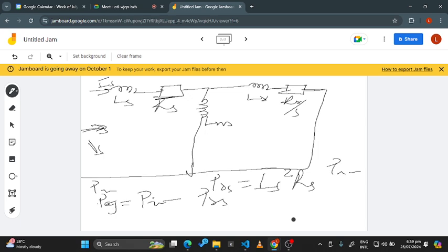As it goes to the rotor, the rotor also has resistance, so you have a certain current IR flowing through RR. There will be current through the rotor. This power moves through a magnetic medium to the rotor. Then there will be some losses in the rotor as well because the rotor has resistance. The total power that gets to the rotor is the air gap power PAG. Some of this power is going to be lost in the rotor, and that power lost in the rotor is called the P slip, the slip power.